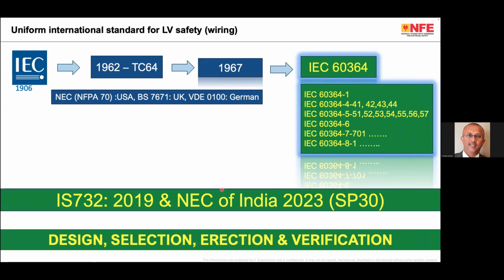The safety measures are very much recommended in the IEC 60364 standard, which is nothing but IS 732 in India, and NEC 2023, which explains design, selection, erection, and verification. Please note that these safety measures are impossible to integrate into one equipment. If somebody comes saying, look, I have a magic equipment which offers all the safety measures, it is impossible. If somebody makes such a claim, it is because the person doesn't know about electricity, doesn't know how safety has to be achieved in an electrical installation.